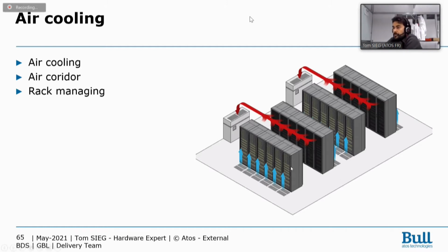Also, all material will be used and arranged for the air flux. For example, you will be able to find a Cisco switch with reverse fan, depending on whether you want your Ethernet connectors at the front or at the rear. For many servers, it's exactly the same. You can have PSUs and fans reversed if you want your front or your back to be hot or cold.